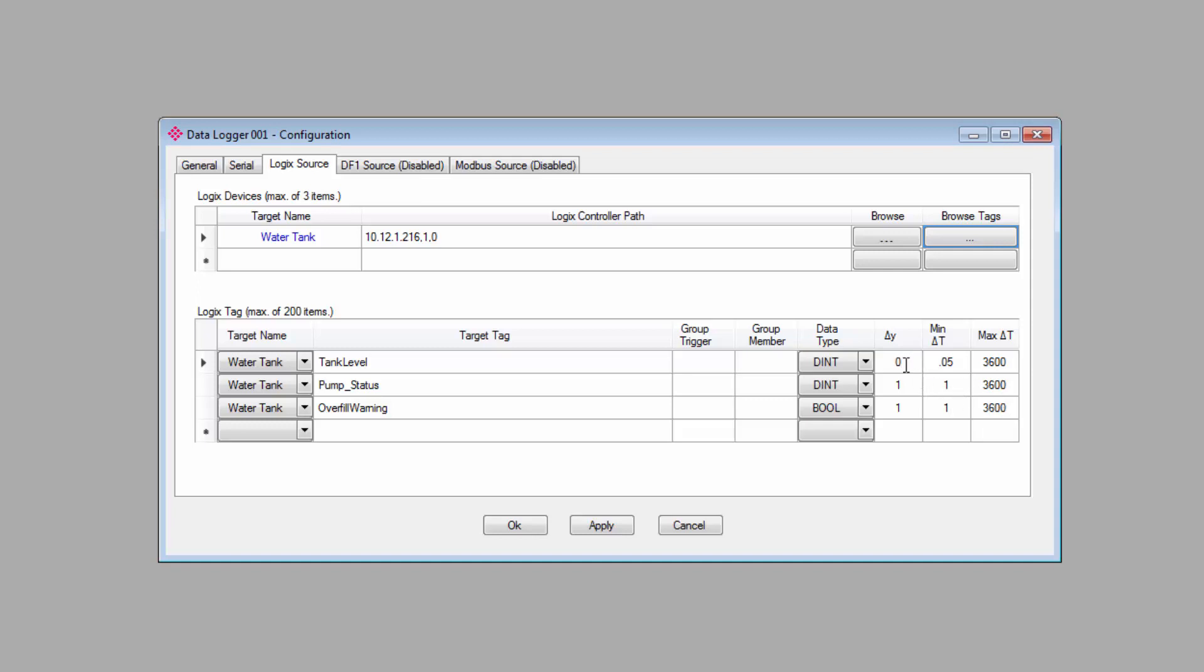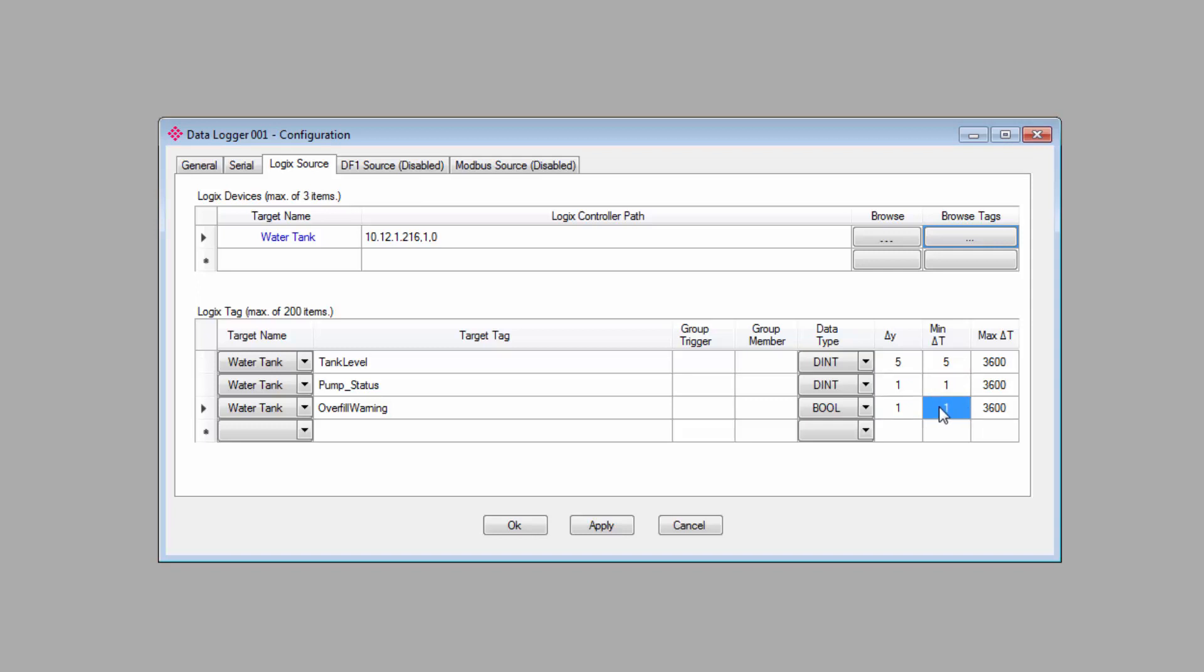For my application, I have a 500 gallon tank. I really don't need to track every gallon in or out, so I'll set the value change to 5 and the minimum time to 5 seconds. My other tags are binary, so I'll leave them at 1 and 1 since I would like to log any change that might occur.